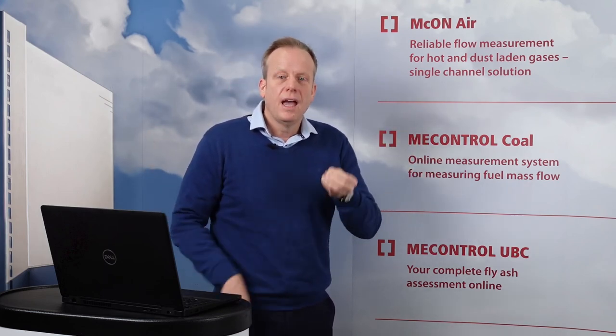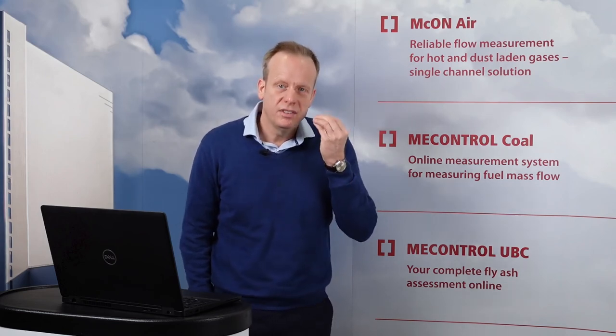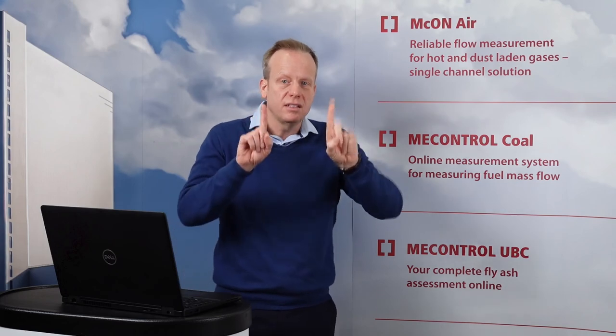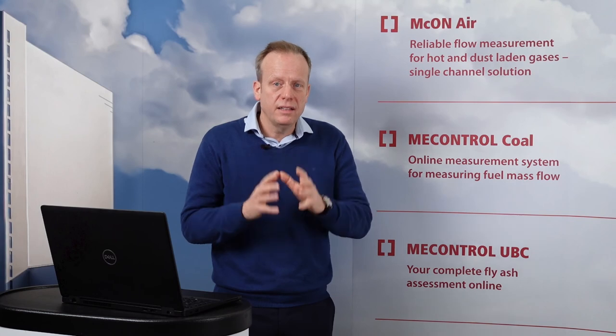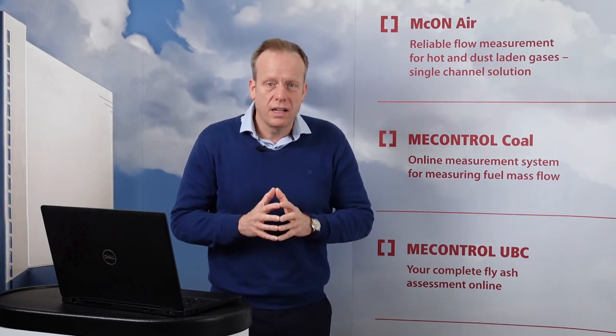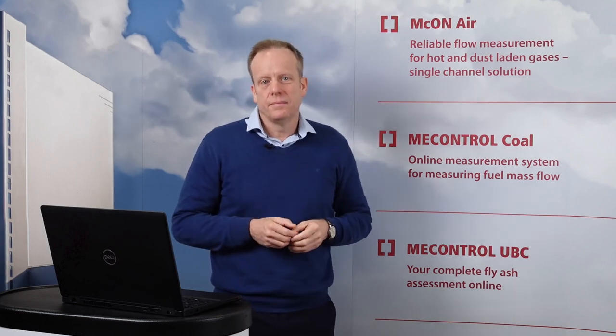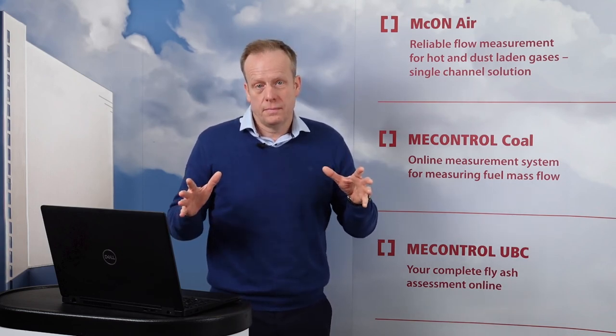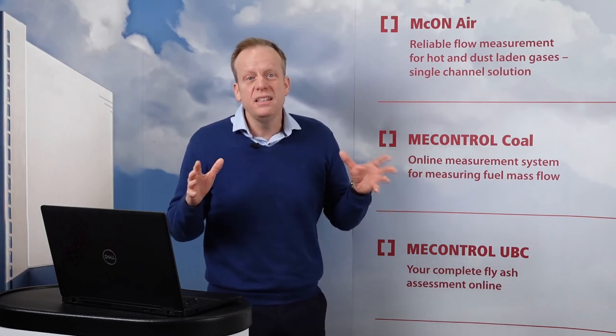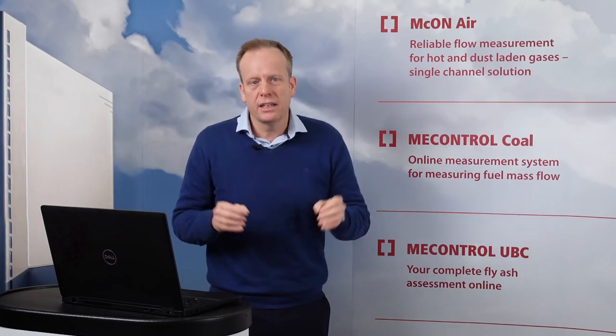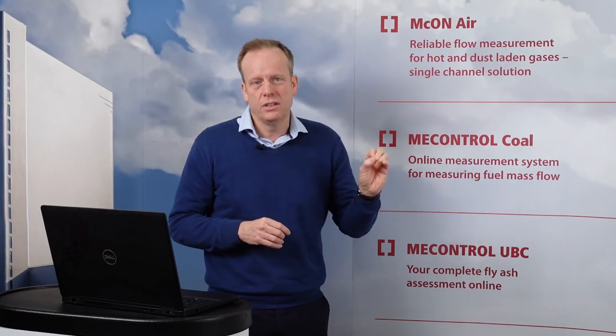So what is our measurement doing? It gives you a digital time measurement, and from this digital time measurement and the sensor distance, we calculate velocity. The biggest advantage for the problem I have described today is drift stability — there is no drift. You can install this and when you check it ten years later, it will have the same accuracy. Because our measurement is digital, it's a big difference compared to analog measurement.